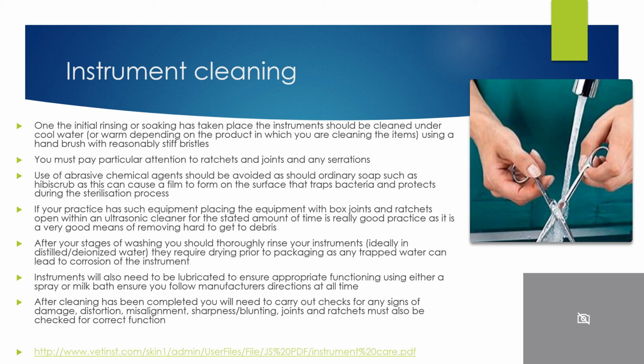After your stage of washing, you should thoroughly rinse your instruments, ideally in distilled or deionised water. They require drying prior to packaging, as any trapped water can lead to corrosion of the instrument. Instruments will also need to be lubricated to ensure appropriate functioning using either a spray or milk bath. Ensure again that you follow manufacturer's directions at all times.